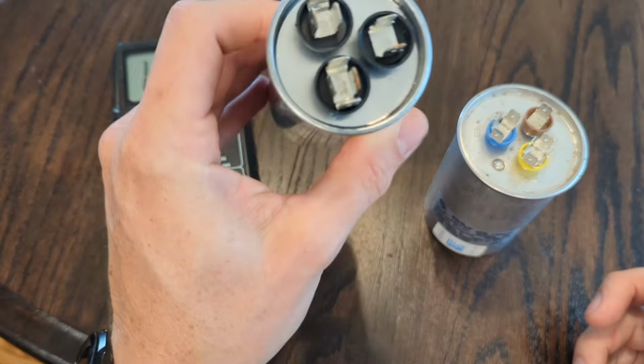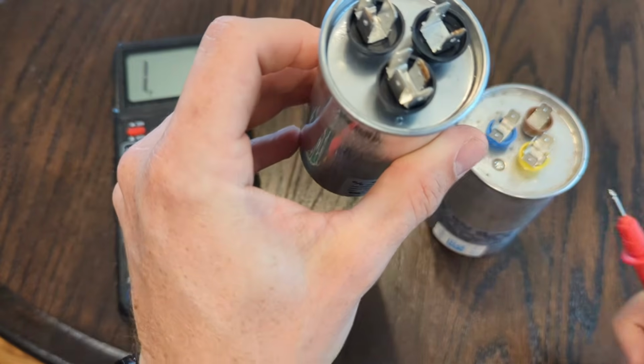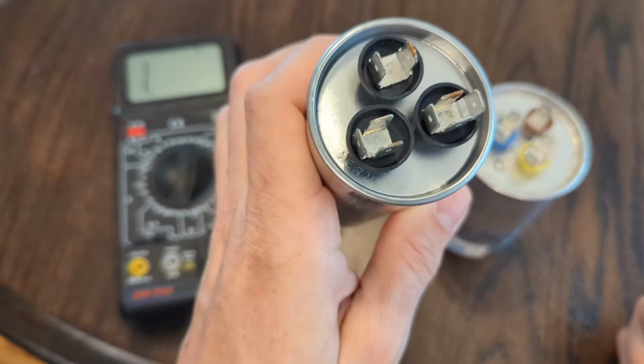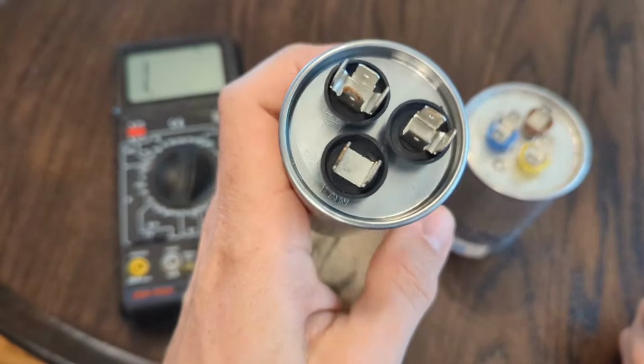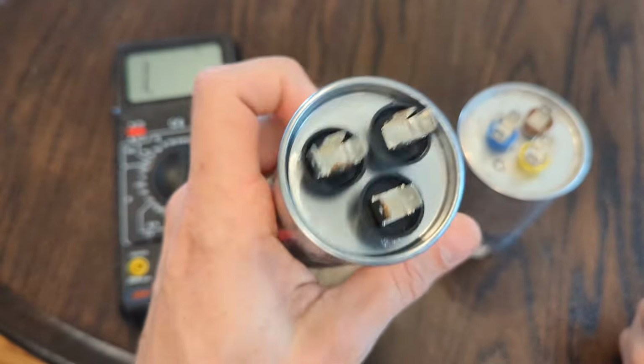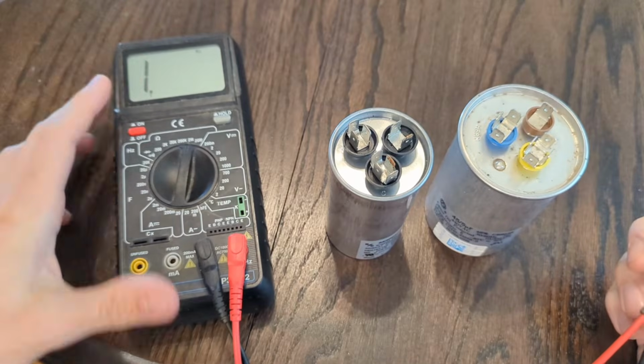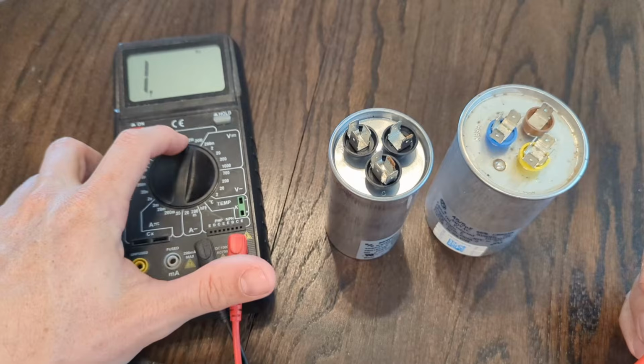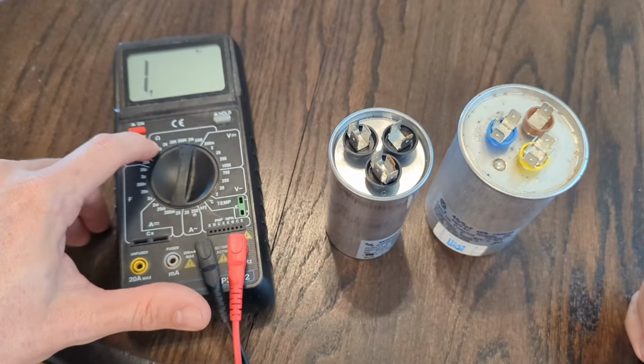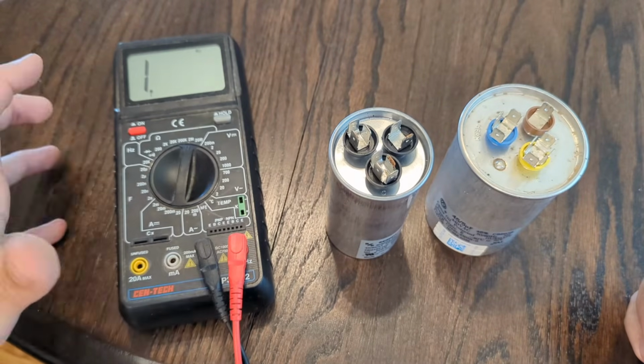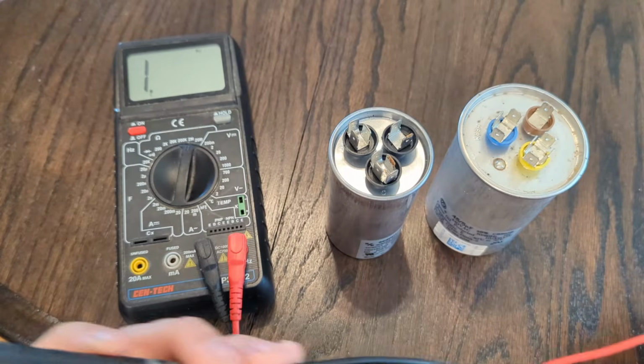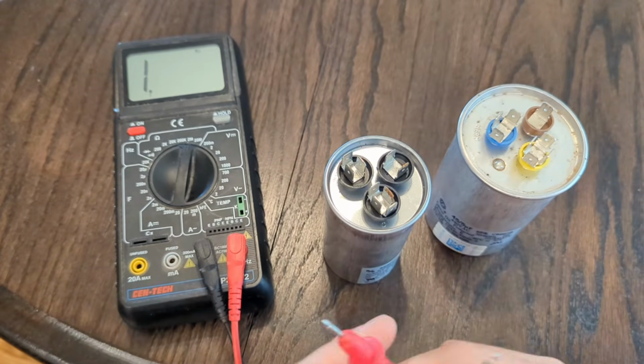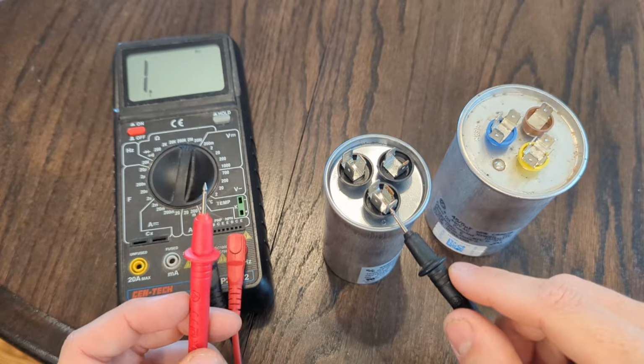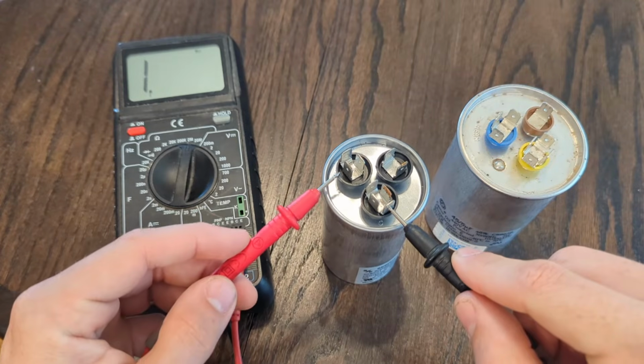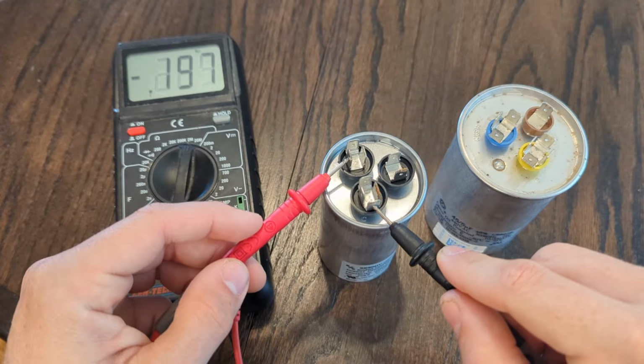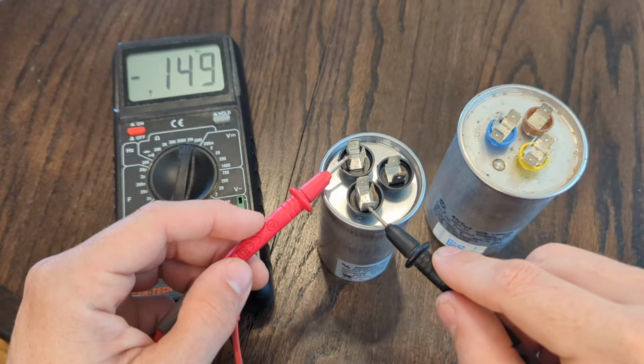So this is the good one. If you'll notice, there's a little C down here at the bottom, and it says Herm. That's for the hermetic compressor, and then there's the fan. Obviously that's for the fan. So first we're going to set this to 2M on the ohm setting, or 2000K, depending on how your multimeter sets it up. Okay, so what we're going to do is take the black lead and touch it to the common side, and the red to the hermetic compressor side, and you see how it jumps?